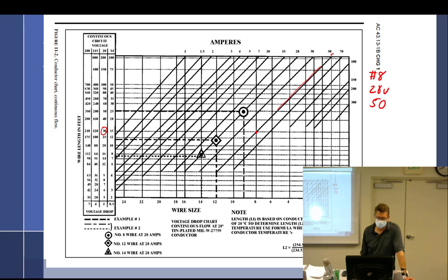Okay, now that's assuming what again? What are my assumptions? Free air and not in a bundle, not in conduit, 100... not over 68 degrees. Okay, right there, voltage drop chart, continuous flow at 20 degrees Celsius, and it does have the part number for that wire. Let me see, I think it's somewhere here, free air somewhere. Okay, but what if, using that same thing, what if the max temp is 50 degrees?